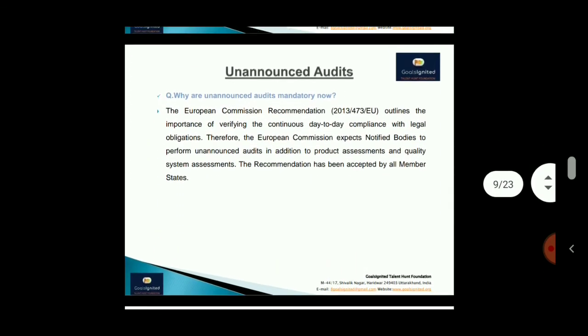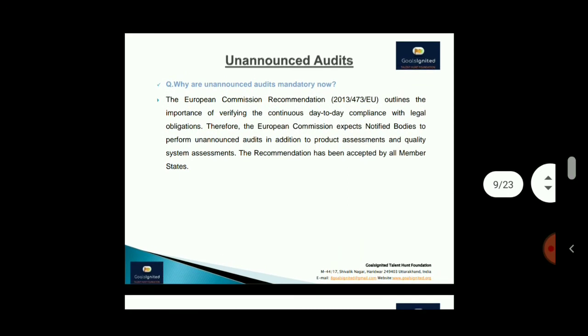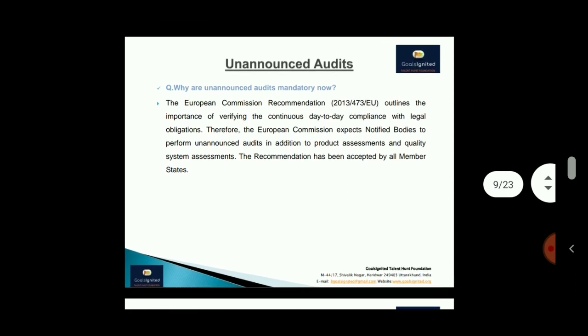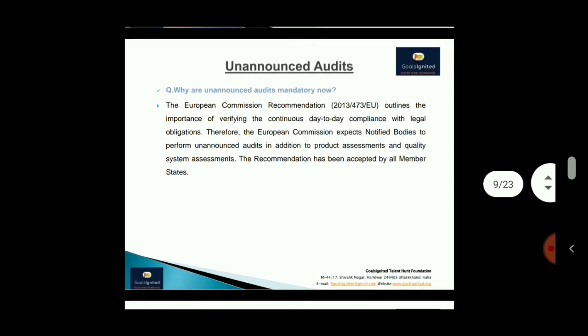So the next question: why are unannounced audits mandatory now? As I told earlier, initially there was the initial audit, then the surveillance audit, but now there is a trend, a requirement, and a law that the unannounced audit is taken as mandatory. The European Commission recommendation outlines the importance of verifying continuous day-to-day compliance with legal obligations, and therefore the European Commission expects notified bodies to perform unannounced audits in addition to the product assessment and quality system assessment.